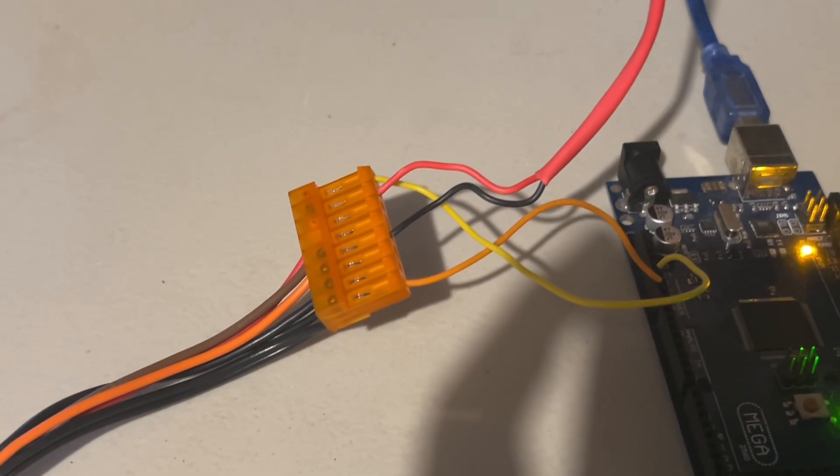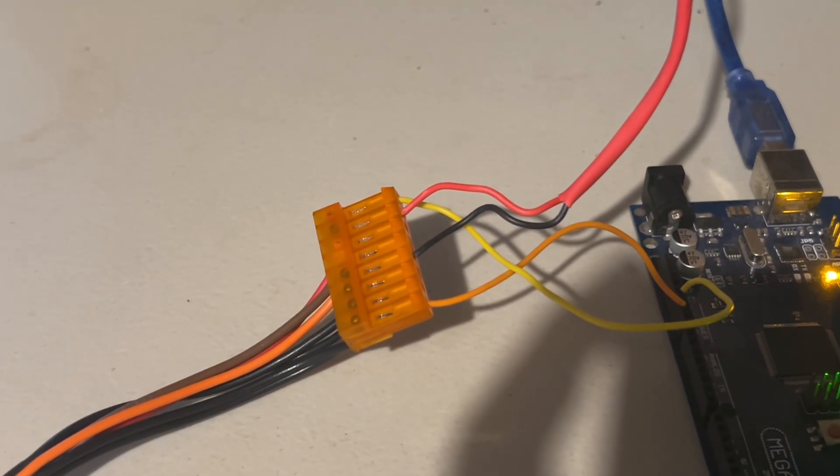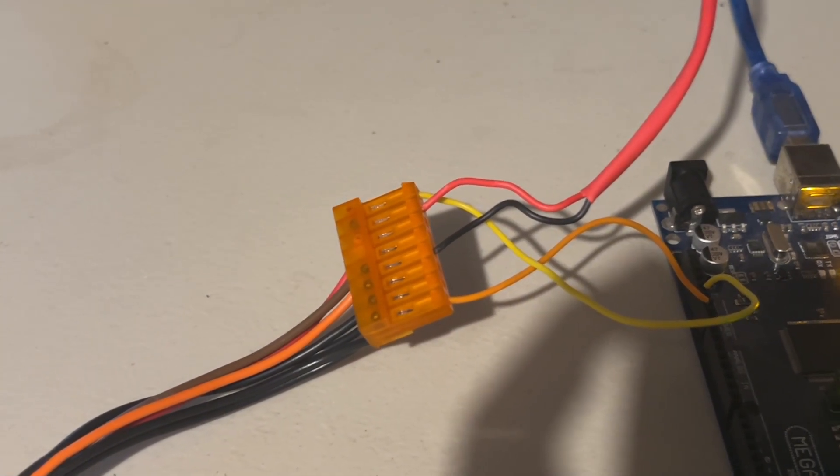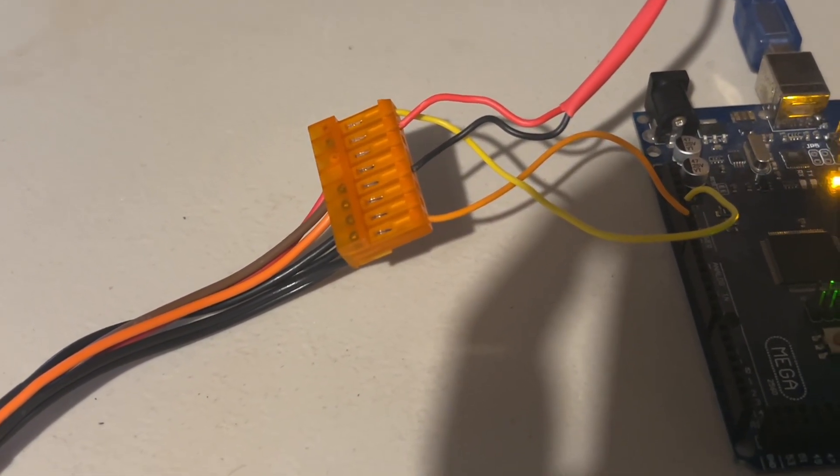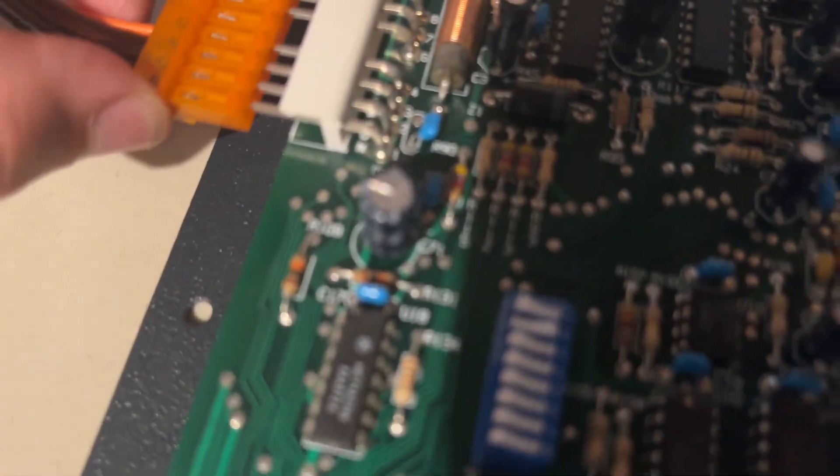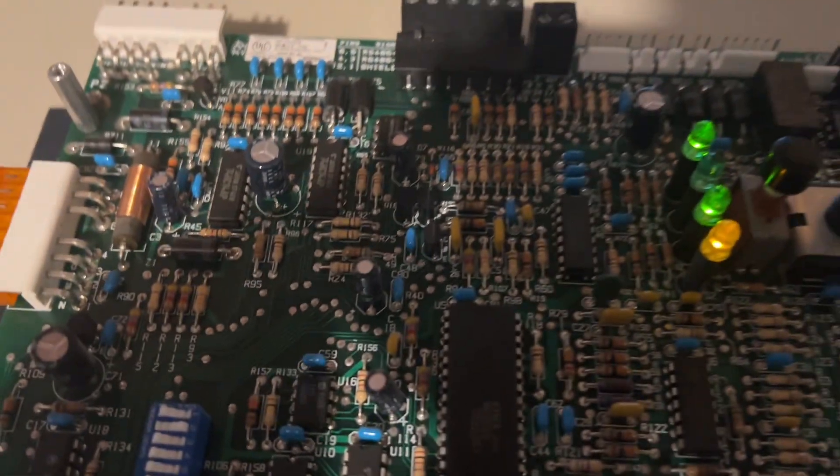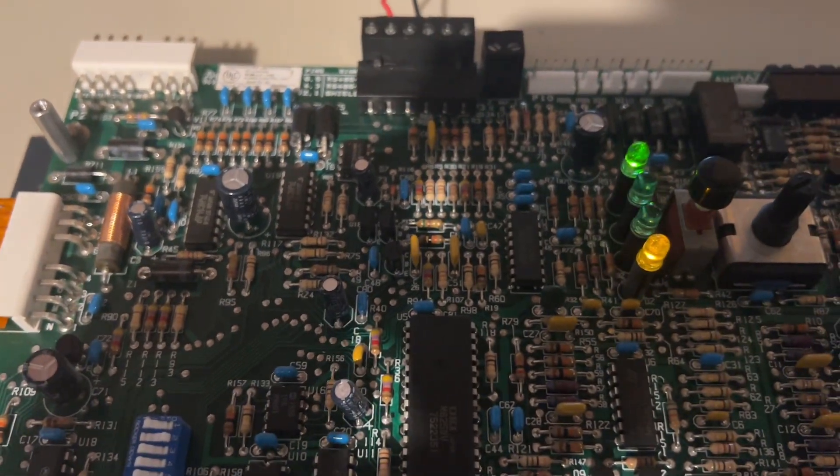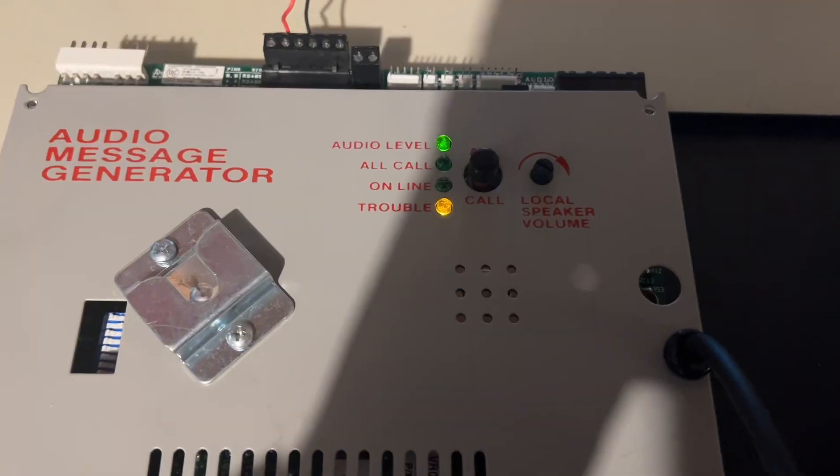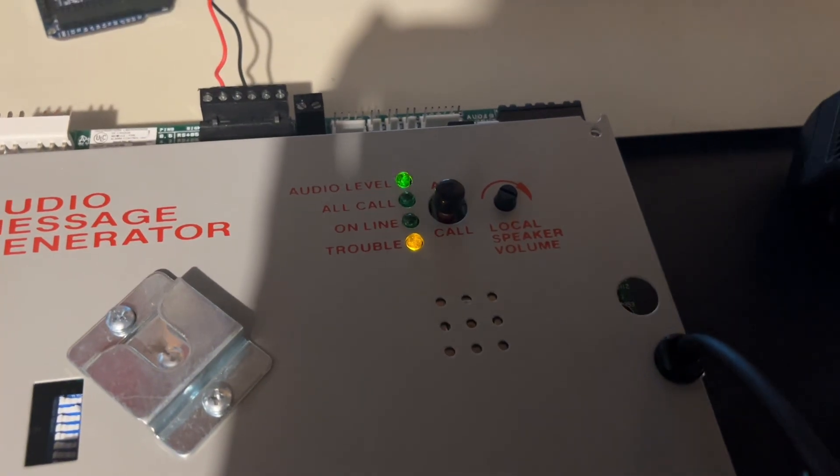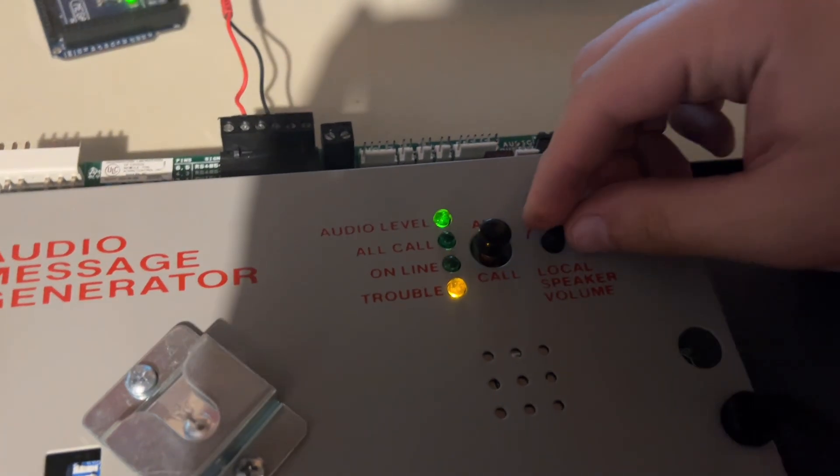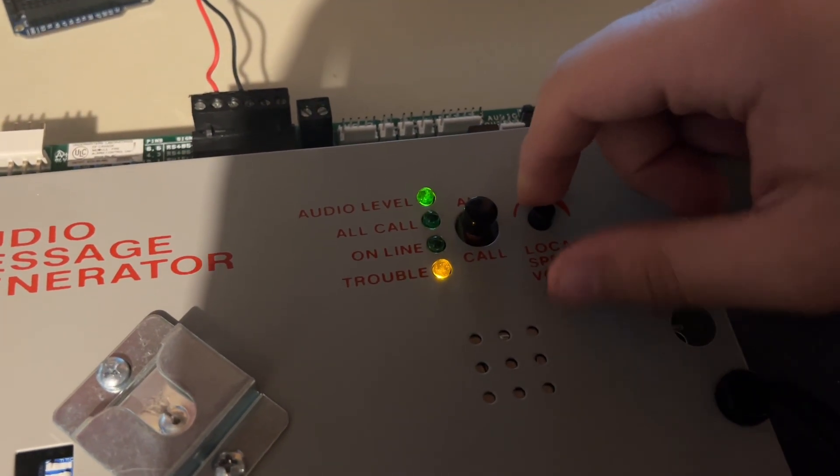Okay, so these are my wiring connections. Yellow is 5 volts. Red is 24 volts. Black and orange are ground. Now it's time to plug it in. I put the cover back in place so I can plug in the microphone and use the local speaker. If I turn it up, you'll hear the supervision tone.